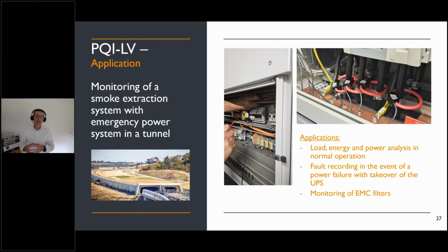In case of an error or something happens in the tunnel, maybe the smoke extraction system runs up, the system is automatically recording a snapshot in case of a fault recorder in the event of a power failure, because a UPS system must run up, and there were many issues in this tunnel in the past, and the German Autobahn GmbH knows about the situation, that it could be unstable, and they want to have an exact snapshot of the true RMS as well as the oscilloscope picture in case of this failure.